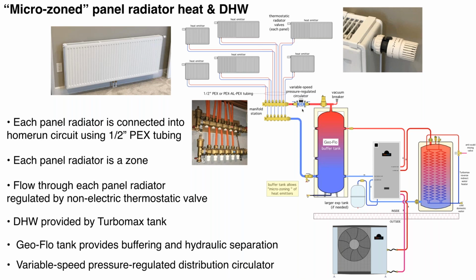And essentially at that point, you've got a system, I'll describe it as cruise control. You've got cruise control on the circulator speed, and you also have cruise control on a room by room basis for temperature. So it's a simple, very repeatable concept where I'm showing 6 panels. There could be 3, there could be 4, there could be 8. You would just scale the manifold up, and it's a really nice tie-in with the heat pump.